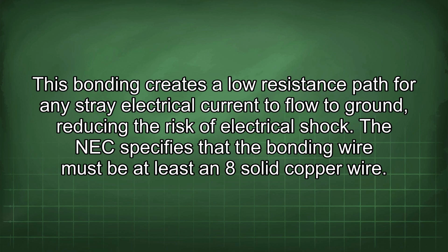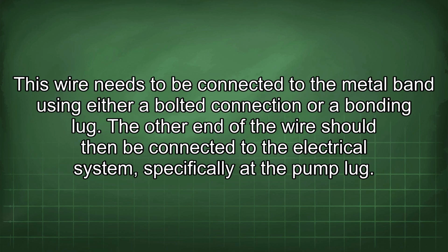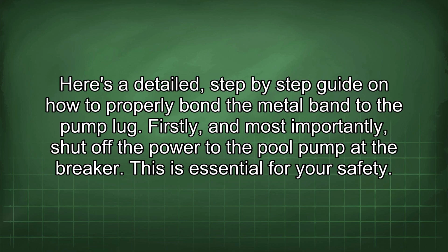The NEC specifies that the bonding wire must be at least an 8-solid copper wire. This wire needs to be connected to the metal band using either a bolted connection or a bonding lug. The other end of the wire should then be connected to the electrical system, specifically at the pump lug. Here's a detailed, step-by-step guide on how to properly bond the metal band to the pump lug.